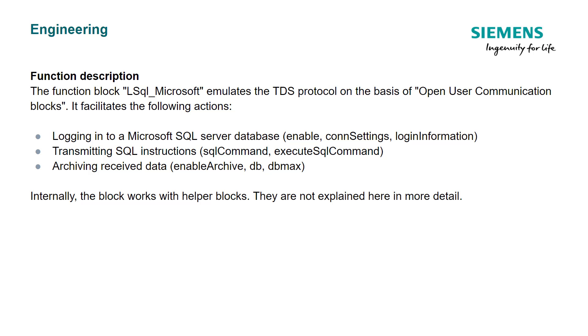The Function Block LSQL Microsoft emulates the TDS protocol on the basis of open user communication blocks. It facilitates the following actions: logging in to a Microsoft SQL Server database — the associated tags here are enable, connection settings, and login information. Transmitting SQL instructions — the associated tags are SQL command and execute SQL command. Archiving received data — the related tags are enable archive, db, and dbmax. Internally the block works with helper blocks, so they are not explained here in more detail.